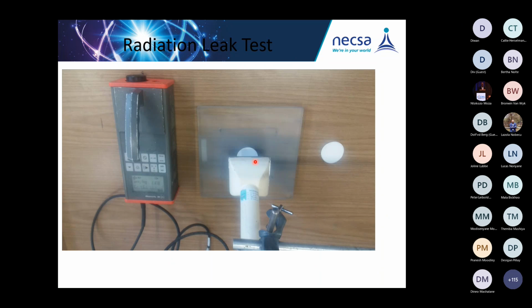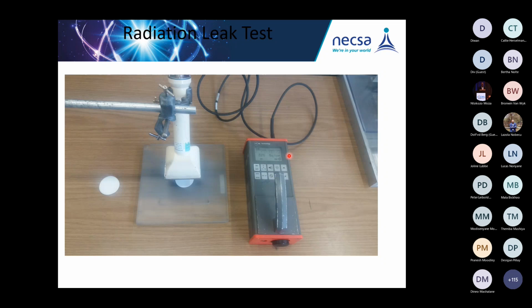This is how you perform it. You place this paper and wipe it around your source or X-ray to check if there is a leakage. The distance between the surface active area of the probe and that source should be as close as you can, at least 4 millimeters. But you shouldn't touch it, because if there is a leakage and that paper is contaminated, then it will contaminate your probe. And then your instrument must be in becquerel per square centimeter, as you can see here.